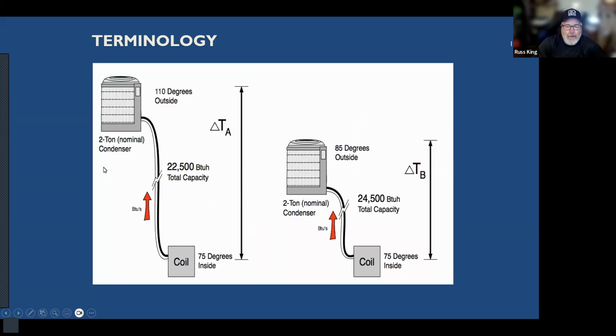So if you've got a 2-ton nominal air conditioner, and you're trying to pump from 75 degrees inside the house, and you're trying to extract BTUs and dump them outside where it's 110 degrees, like in Las Vegas. Okay. We call that the delta T, the difference between the indoor and the outdoor temperature. And this 2-ton nominal air conditioner, which is rated at 24,000 BTUs, may only give you 22,500. So something less than 24,000 BTUs. But if it's only going from 75 degrees up 10 degrees to 85, it might actually give you a little bit more than 24,000. Okay.